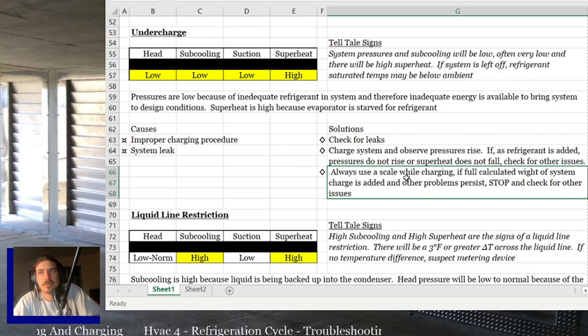Charge the system, and observe the pressures rise. If refrigerant is added and the pressures do not rise or superheat does not fall, check for other issues. I put another note in here. Always use a scale while charging.